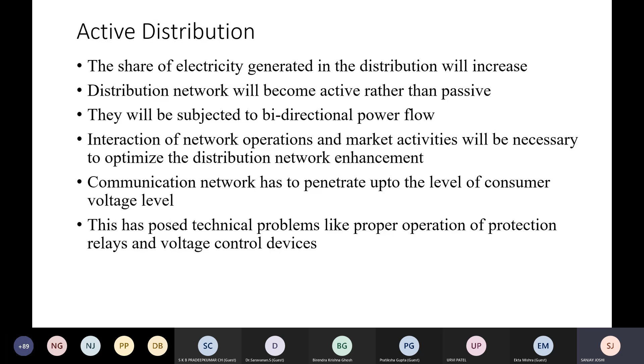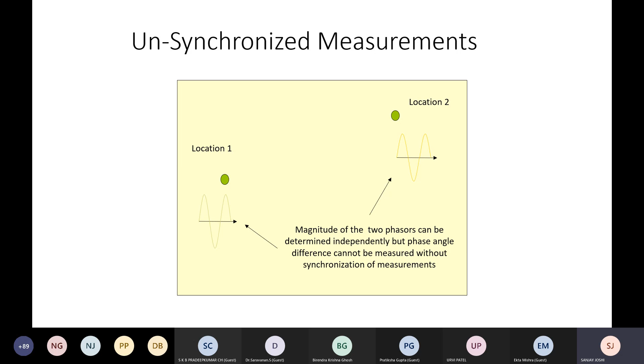Let's now talk about how to make the transmission system smarter. The wide area measurement system. Here unsynchronized measurements are shown. The magnitude of two phasors can be determined using SCADA, where unsynchronized measurements are there across location 1 and location 2. In case of PMU, which gives you synchronized measurements, you can see the two vertical lines. So that shows the time reference, right? And because of the accurate time reference, phase angle difference can also be measured using the PMU across the two locations, right? So these are the waveforms of voltage at location 1 and location 2.